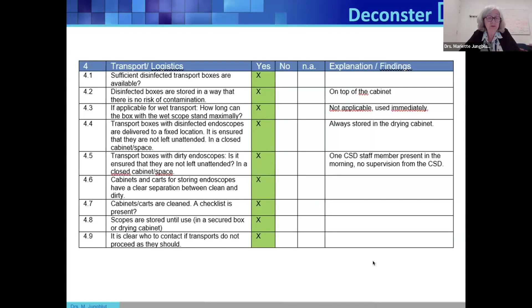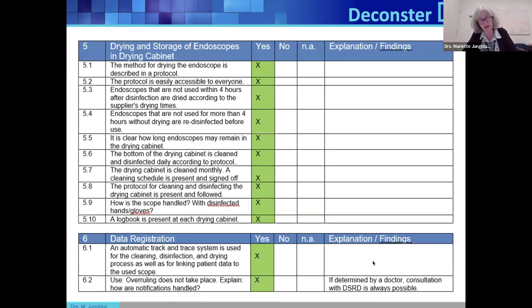Drying storage has to be cleaned every day. Once you take an endoscope out, you have to clean and disinfect the storage cabinet. By the way, we use a drying cabinet as well as a storage cabinet, but that's not really necessary. You can also use it as a drying cabinet to dry and then put the scope into closed boxes. It's fine with me as well. And you can keep it for 1 month. After 1 month, the scope has to be mechanically disinfected again before use.